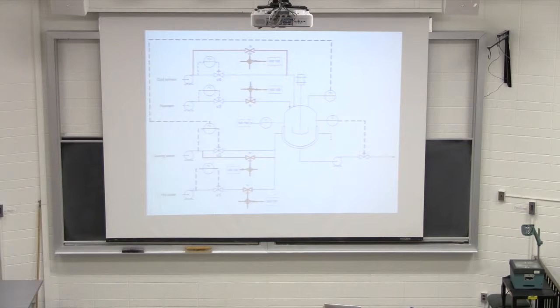And here in this case, we said we don't want an unsafe exothermic reaction to run away. So we've got this very high temperature developing in the CSTR. What we will do is we'll measure that temperature. We use one thermocouple, a second, or a third, to really get an accurate hold on the temperature reading to trigger the SIS.